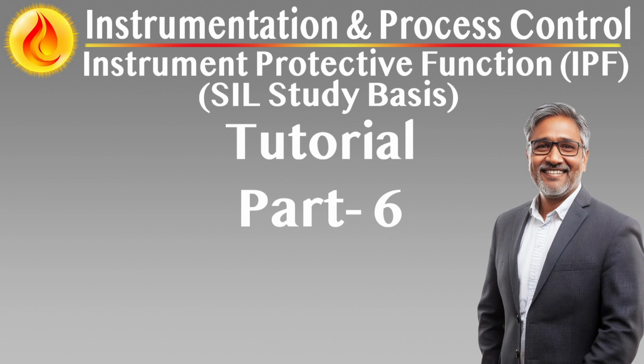Functional independence must be maintained. Communication must not create logical or physical dependencies between the IPF and non-safety systems. IPFs must remain capable of executing their safety function independently of the availability or correctness of external systems.